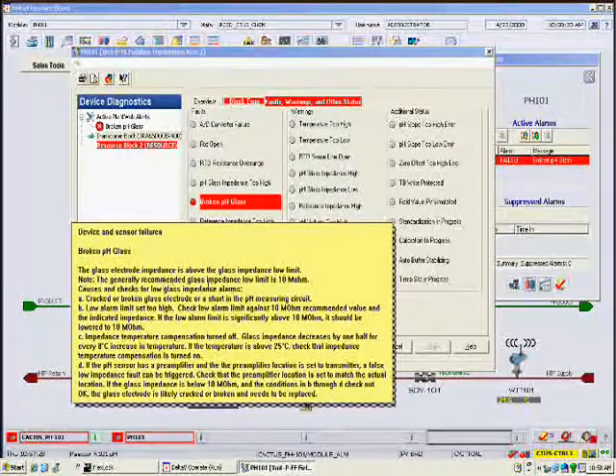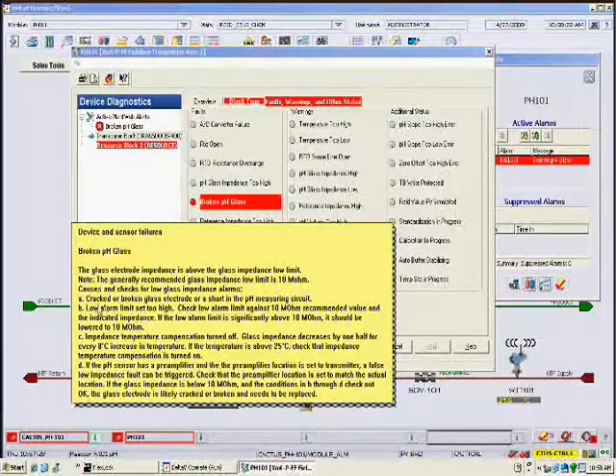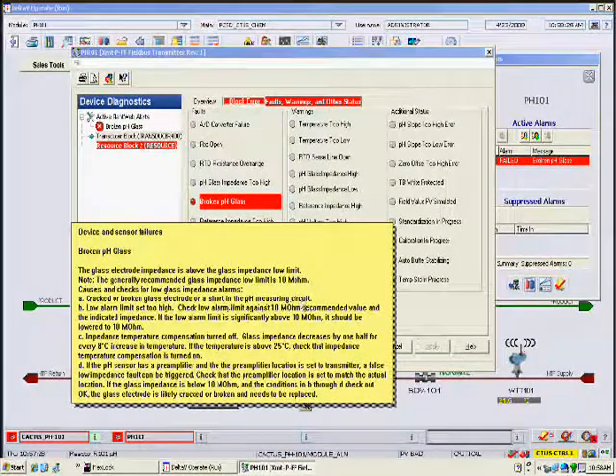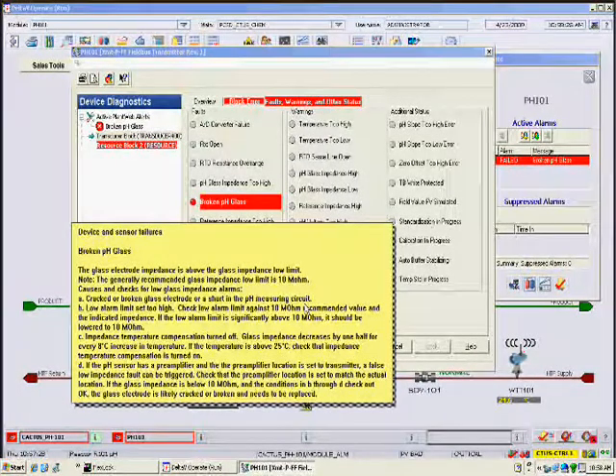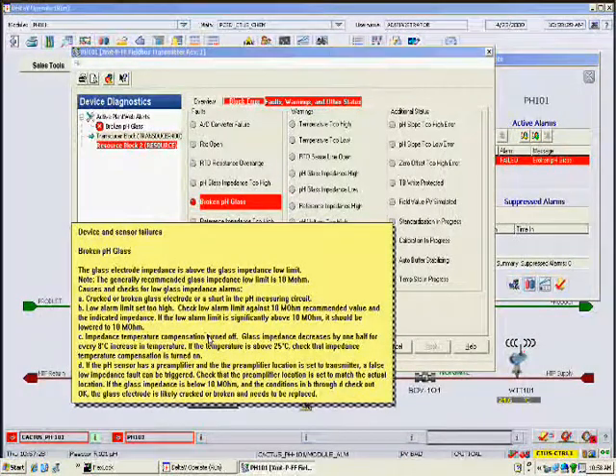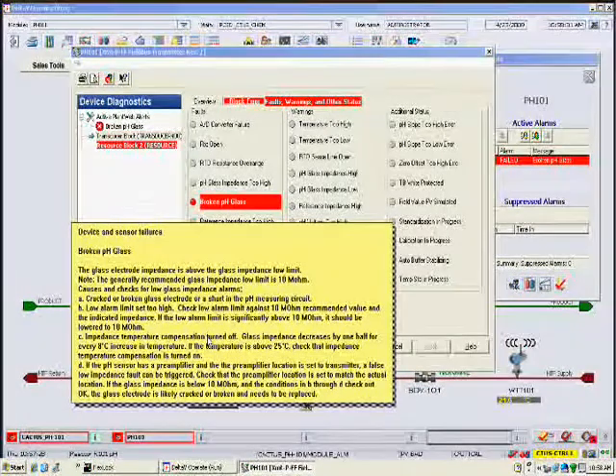The operator clicks on the help button and then on the failure indication. Help text for the failure appears. The help text is provided through the EDDL file by the device manufacturer's expert who knows the product best. Actionable information guides the user towards the appropriate action. The operator cannot fix the problem sitting at a console, but can radio a technician in the field with the details, enabling the problem to be fixed quickly.